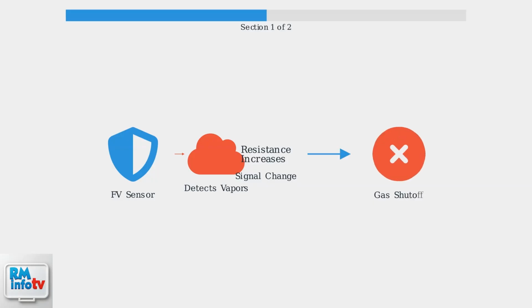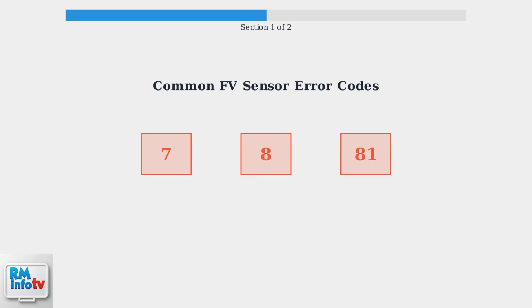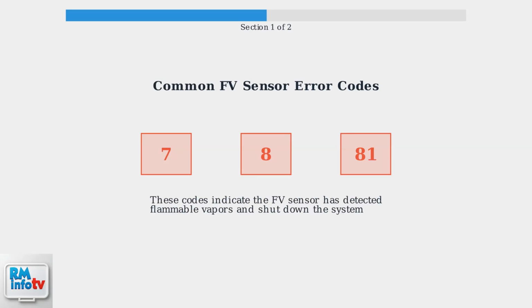The FV sensor works by monitoring air quality and detecting flammable vapors such as gasoline, paint fumes, or household chemicals. When these vapors are detected, the sensor increases its electrical resistance, which signals the gas valve to shut off immediately. When the FV sensor is triggered, your water heater will display specific error codes. The most common codes indicating a tripped FV sensor are 7, 8, or 81. These codes appear on the display panel of power vent or direct vent water heaters.